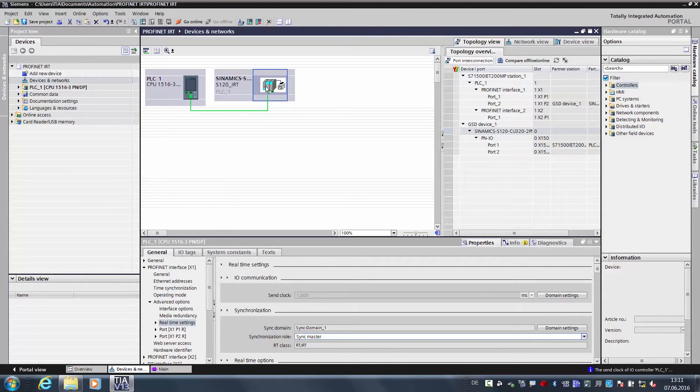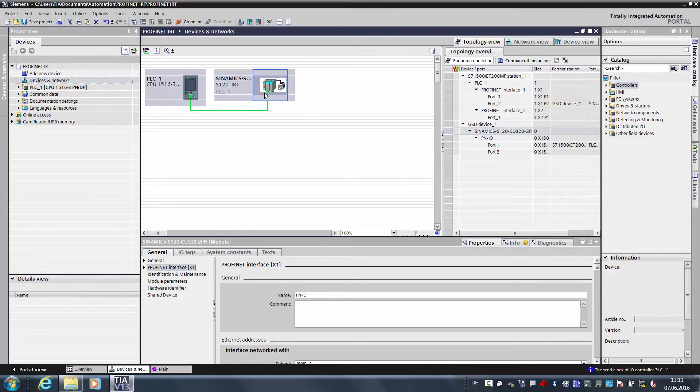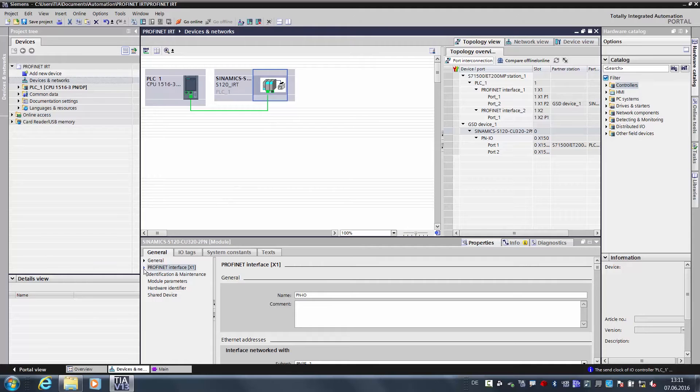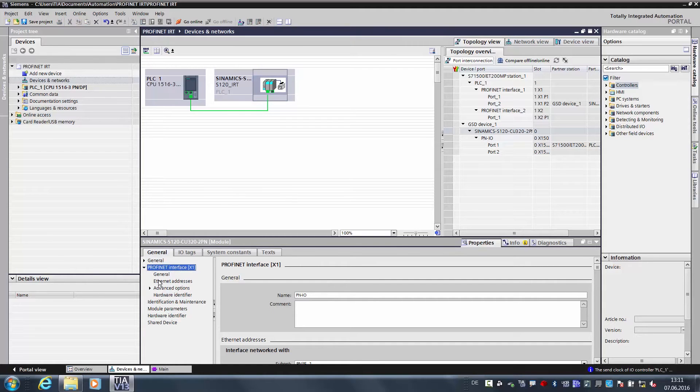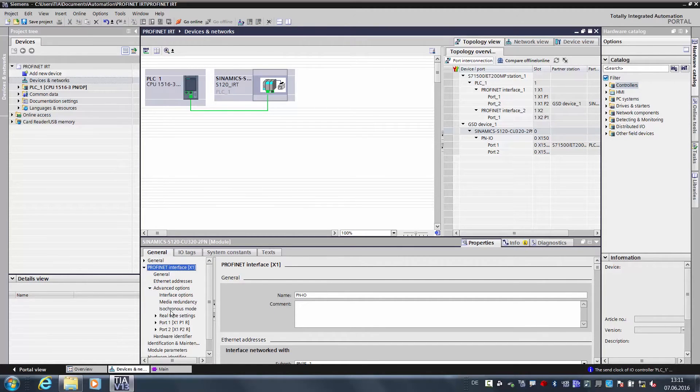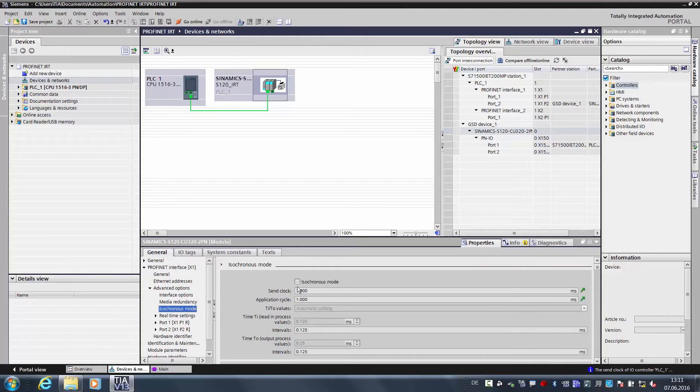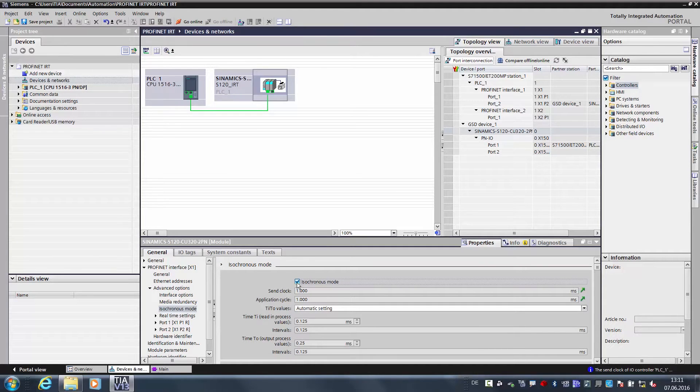The next thing we need to do is to configure the Isochronous Mode for the SINAMICS S120. To do so, we once again go to the PROFINET interface of the drive, Extended Settings, Isochronous Mode, and we also check the box here.